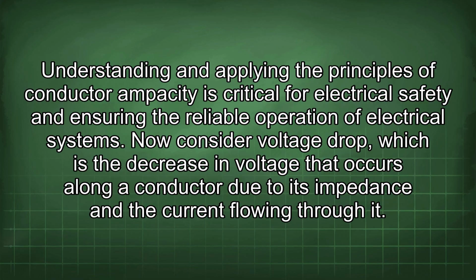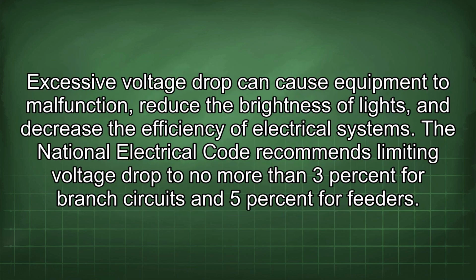Now consider voltage drop, which is the decrease in voltage that occurs along a conductor due to its impedance and the current flowing through it. Excessive voltage drop can cause equipment to malfunction, reduce the brightness of lights, and decrease the efficiency of electrical systems. The National Electrical Code recommends limiting voltage drop to no more than 3% for branch circuits and 5% for feeders.